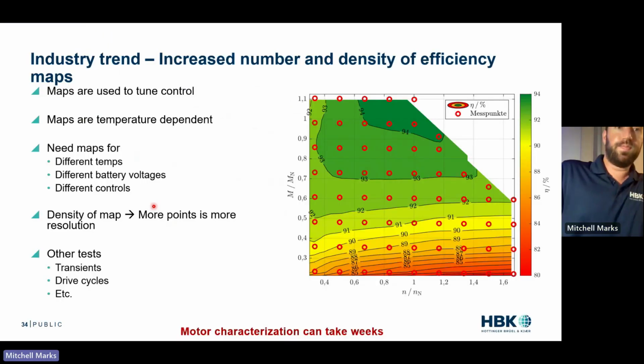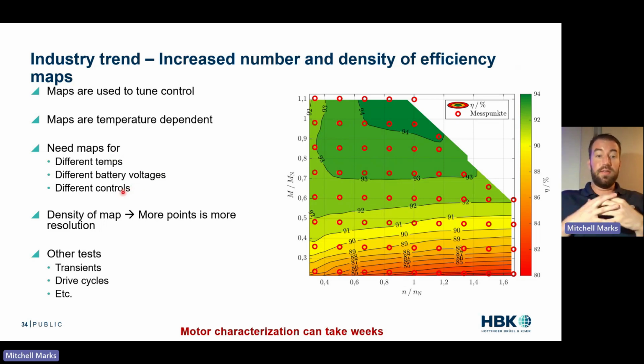All right, test acceleration. We're seeing an industry trend for an increased number and an increased density of efficiency maps. These maps are used to tune our controller. These maps are temperature dependent, and we end up needing different maps for every temperature, every battery voltage, different controls. We end up having tons of maps. And we're seeing another trend towards more density in the efficiency maps, which means more points of resolution. And then there's other tests as well. What we have is, you take a torque and speed, measure efficiency, torque and speed, measure efficiency, and then you get this contour. Because of the number of maps, because of the number of points, we're seeing people go to 25 maps or so, wanting to go to more. We're seeing people go to thousands of points. They used to do hundreds, now they're doing thousands, and this can take weeks.